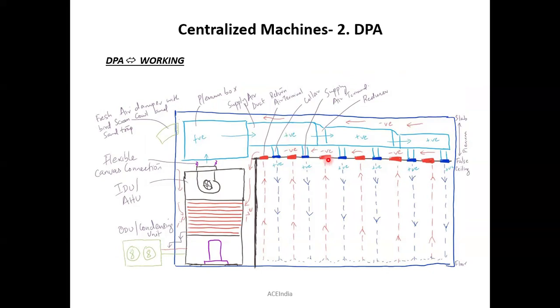And regarding the same scenario from a DSA, we studied that the hot air should be rejected maybe to the plenum area, isn't it? These DPAs are placed right inside a room, isn't it? I told you initially DPA requires a room for the installation, and it should typically be connected this way itself. So these DPA rooms don't have any kind of false ceiling connection, and it always should be open. In other words, the entire return air should be terminated right into the DPA room itself. All right, is it clear, guys? Once again, you can see right here itself, this DPA room doesn't have any false ceiling. In other words, the entire return air should be terminated right into the DPA room. Why? Because it doesn't have any false ceiling, so it should be freely open.